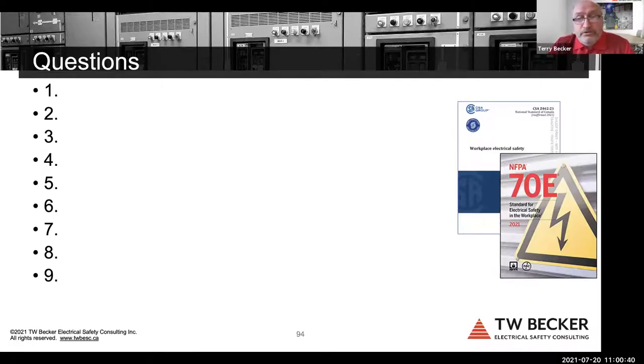So if you open up a hinge door and it's fully guarded and insulated and finger safe, there's no shock hazard, but your interaction, because 70E and Z462 are work task based in Table 130.5(C) and in Table 2. So there's 31 work tasks listed. You need to take that task table and make it your own task table and change the descriptions, change it up, add voltages, because some of the tasks don't have voltages on the voltage where an abnormal arcing fault can be sustained, right?